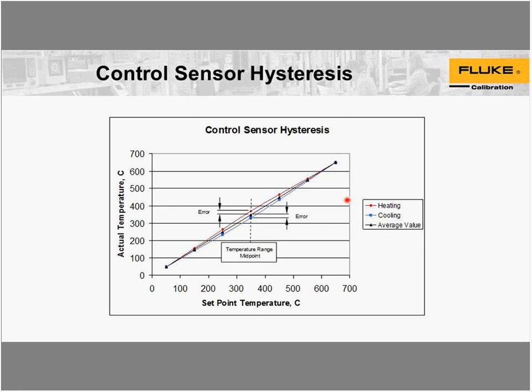So the windings, in the case of a wire-wound PRT, are somewhat restrained, so that it will not shift nearly as drastically when it's dropped. You could expect some shift, but it will not be drastic, and it will also exhibit some hysteresis. That's because the stress of the thermal expansion is holding back some of that wire, so that its resistance behaves in this fashion.